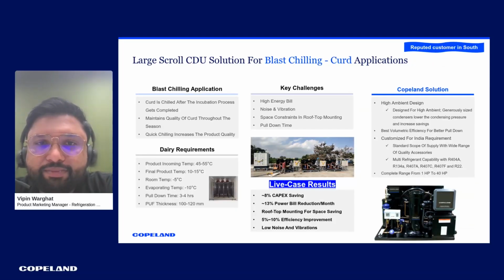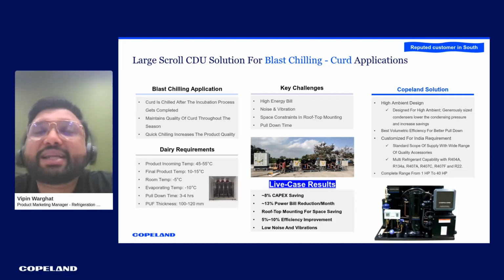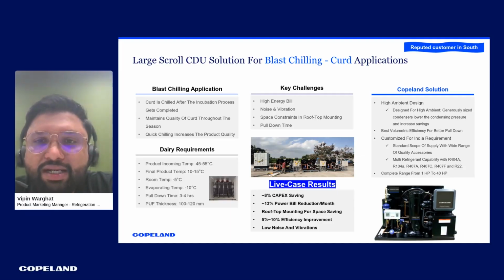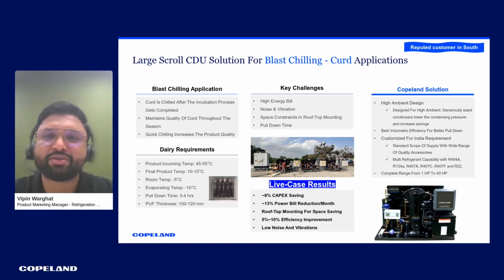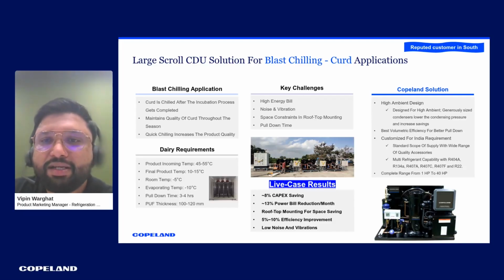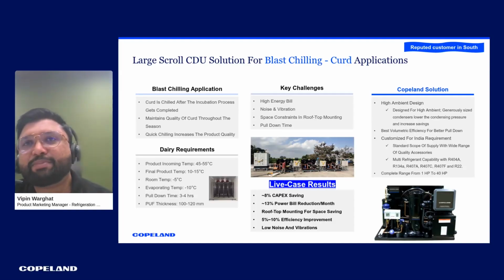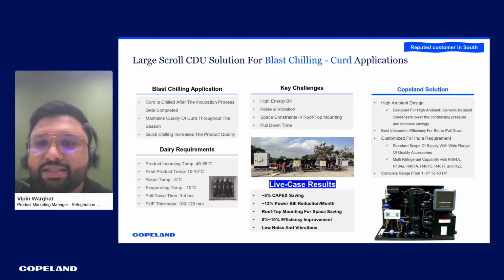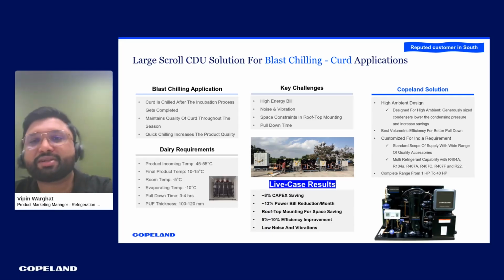Yeah, so this is an interesting application where the customer had a lot of challenges in maintaining their blast chilling application. The challenges faced by the customer were a high energy bill, higher noise and vibration of the semi-hermetic system, and it was consuming space and was heavy, so it was basically placed on the ground, while there was a lot of space available on the roof. It was also not able to deliver the required pull down.